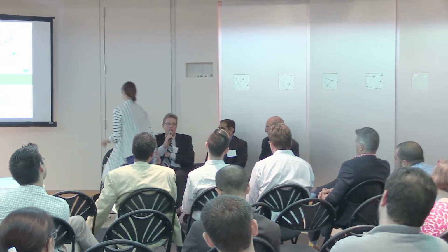The manufacturing of medical devices requires a process of validation to ensure that devices do what they were intended to do. With the fact that you guys are dosing, or making not recommendations, but ensuring that patients have taken the right amount of doses, have you given thought to validating your applications? Yeah, my application is fully validated, and it's gotten through third-party approvals for ONC and for HIPAA compliance. So there are software validation tools it has to go through, yeah.